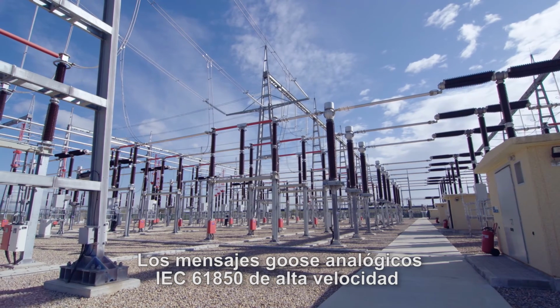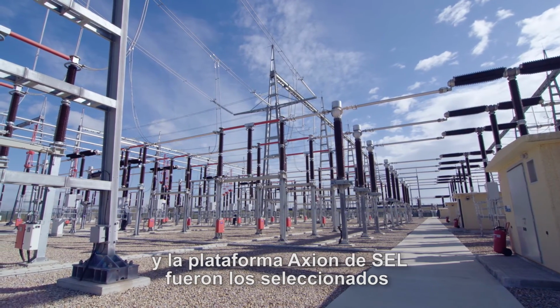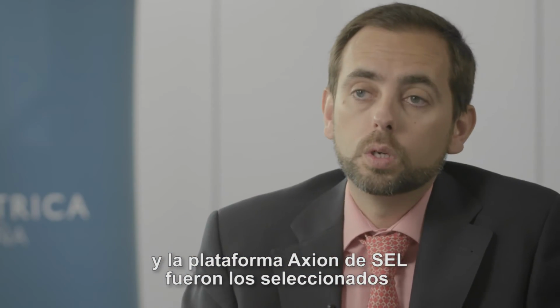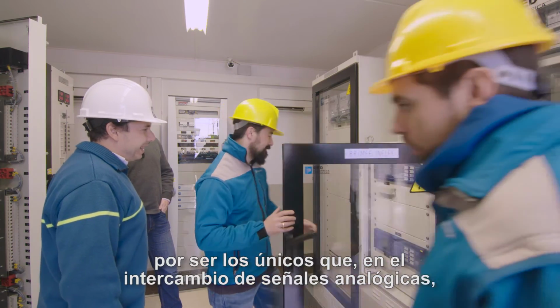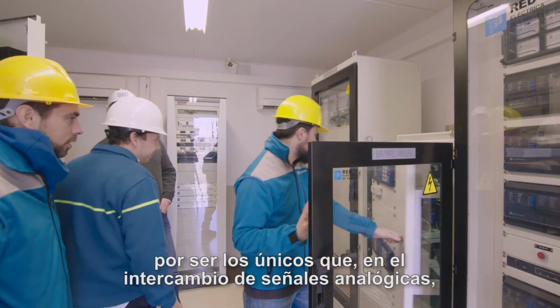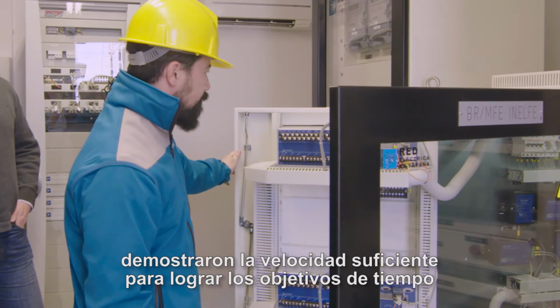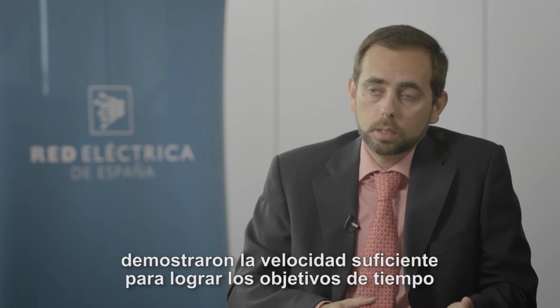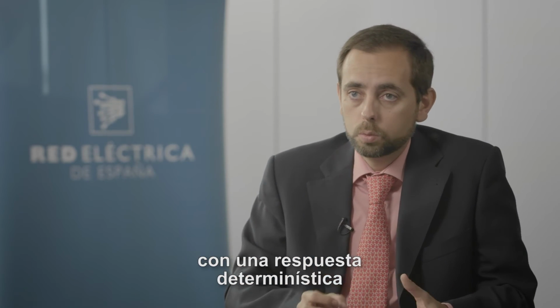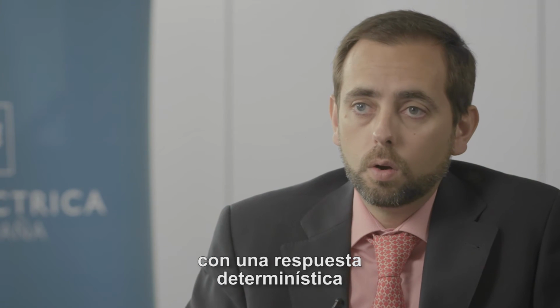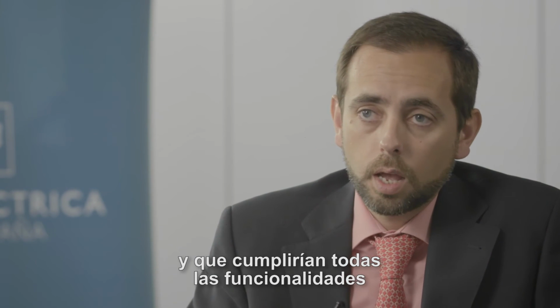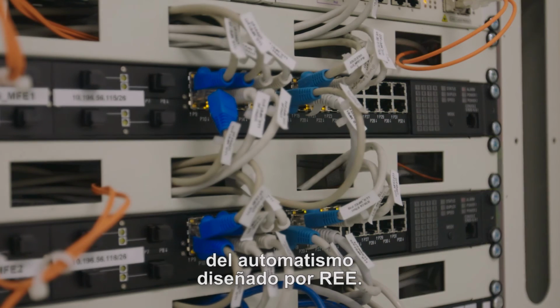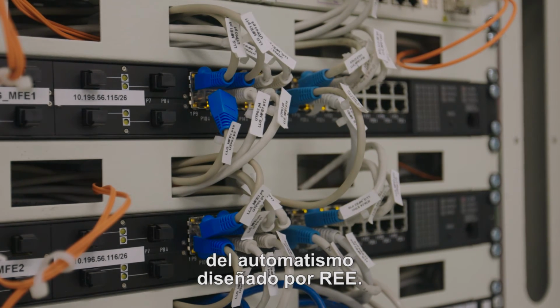High-speed analog IEC 61850 GOOSE messages and the SEL Axion platform was selected because of its unique ability to provide power measurements fast enough to meet the time budget with a deterministic response, fulfilling all REE design requirements for this MFE project with fully compatible devices.